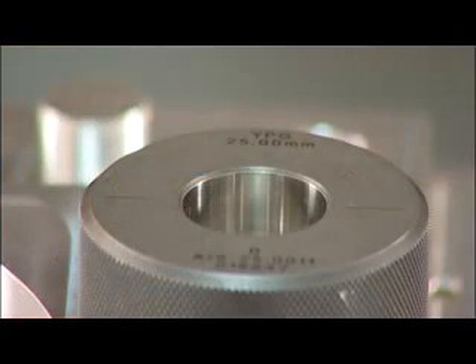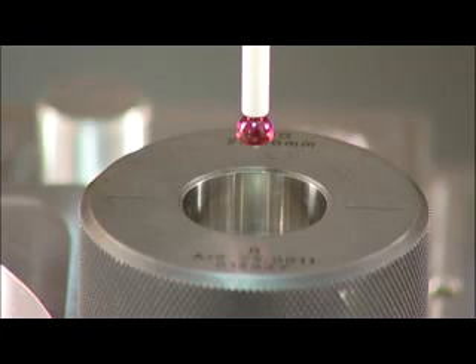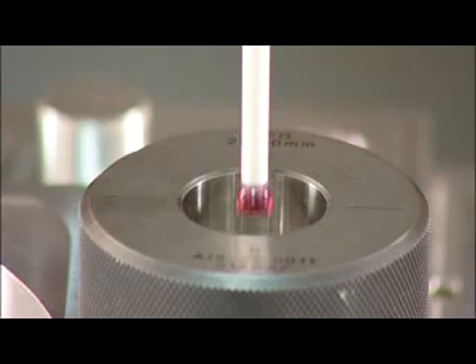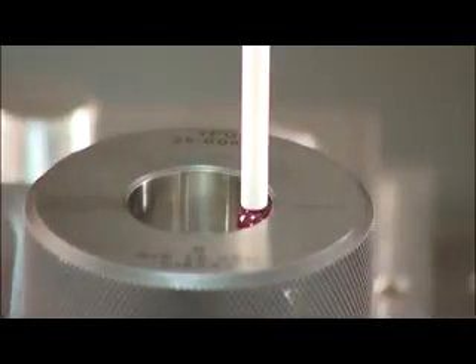The user calls the macro program, then positions the probe in X, Y and Z to the center of the ring gauge in the previously recorded positions. The stylus accurate ball diameter and the ring gauge diameter are now manually loaded into the calibration cycle. The calibration cycle is then run.